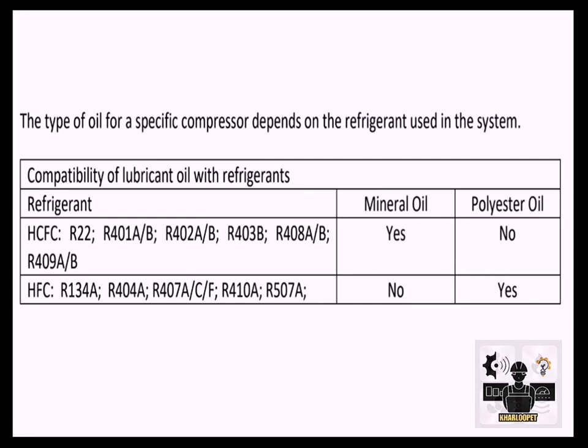Compatibility of lubricant oil with refrigerants: For HCFC refrigerants R22, R401A/B, R402A/B, R403B, R408A/B, and R409A/B — Mineral Oil is used. For HFC refrigerants R134A, R404A, R407C/F, R410A, and R507A — Polyester Oil is used. That's all. Thanks for watching.